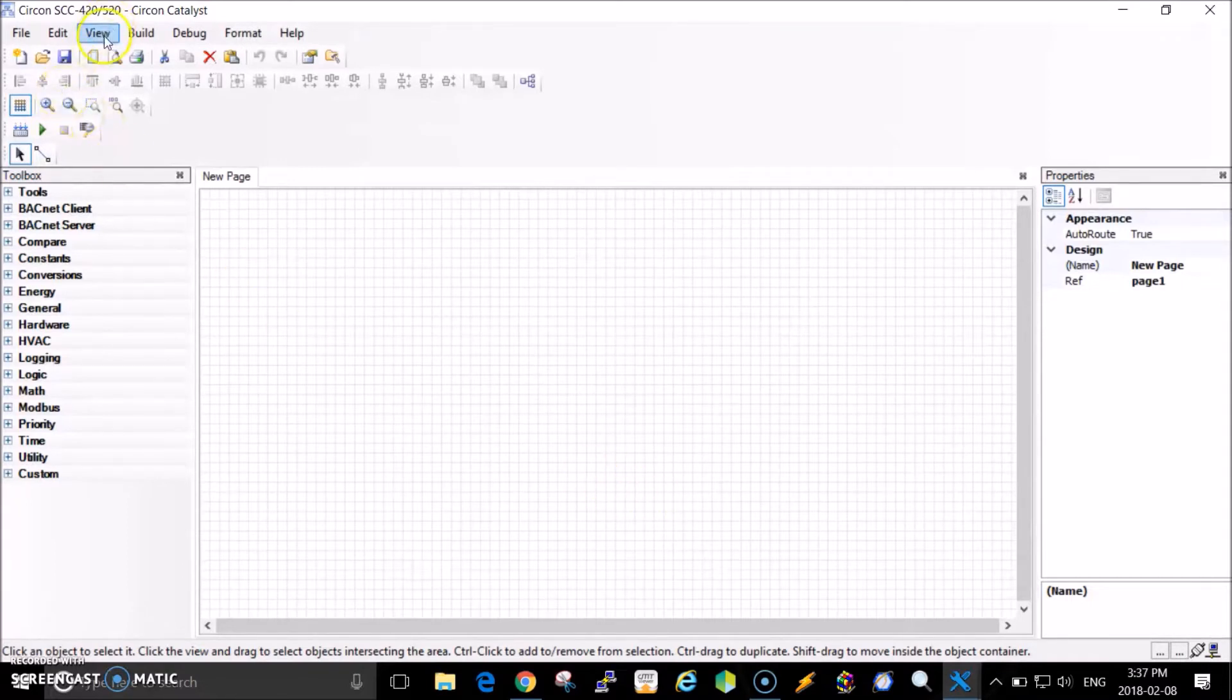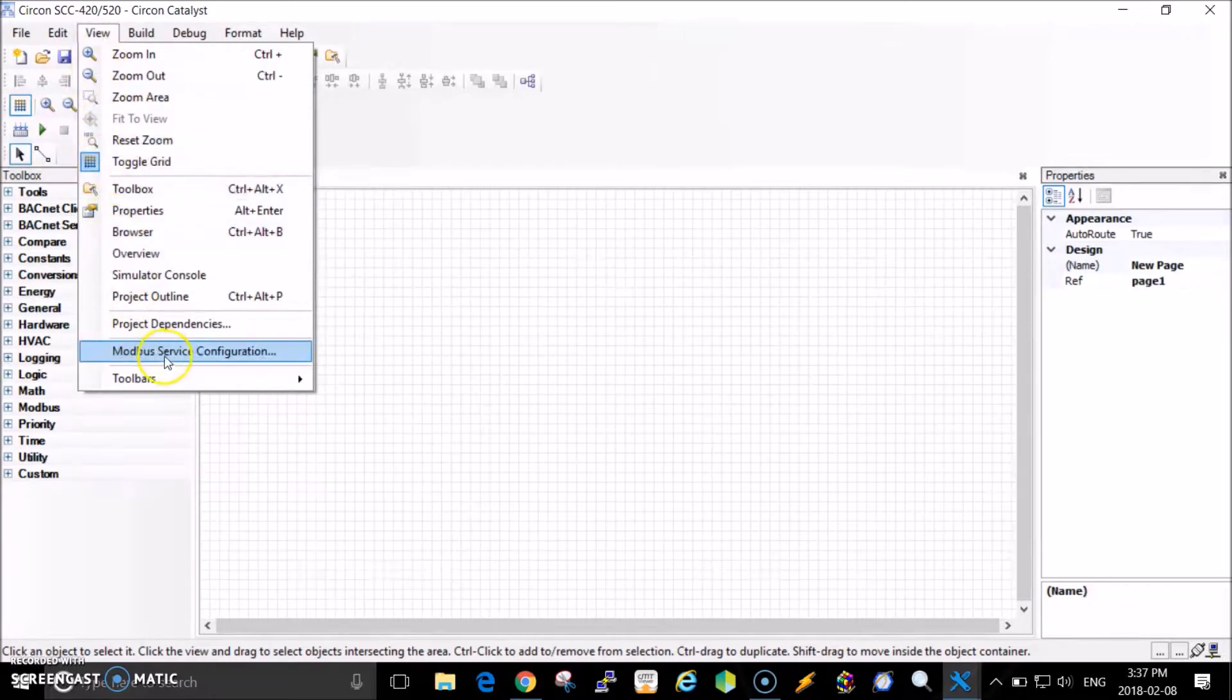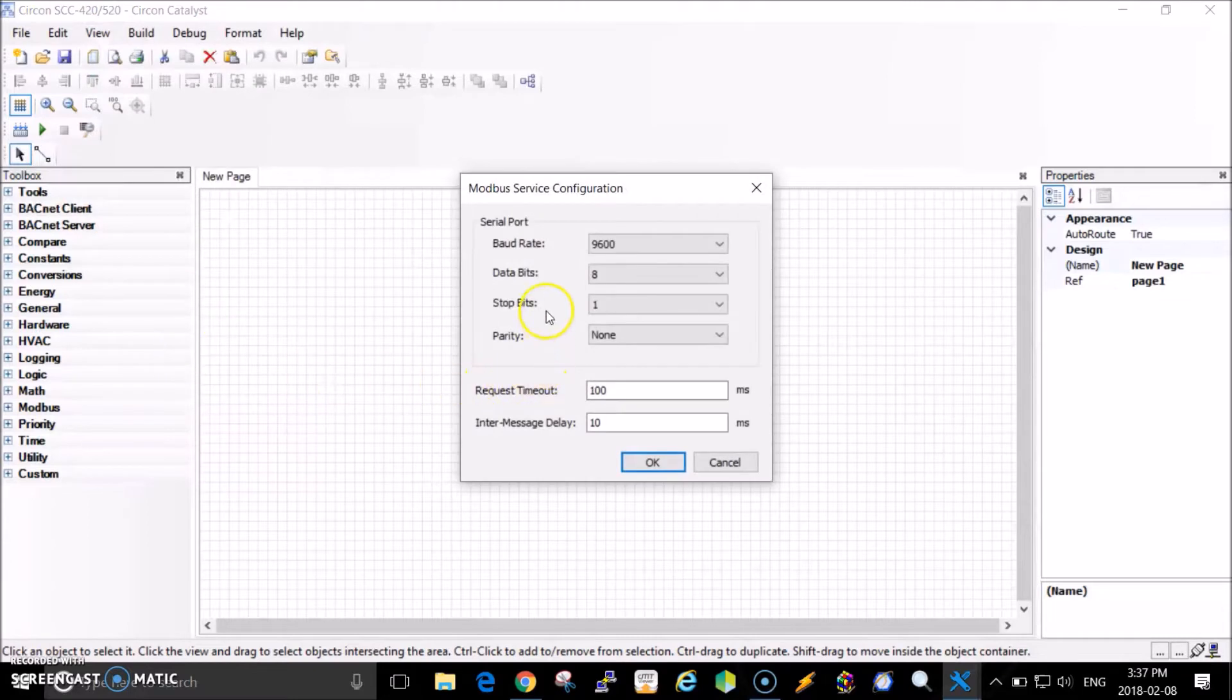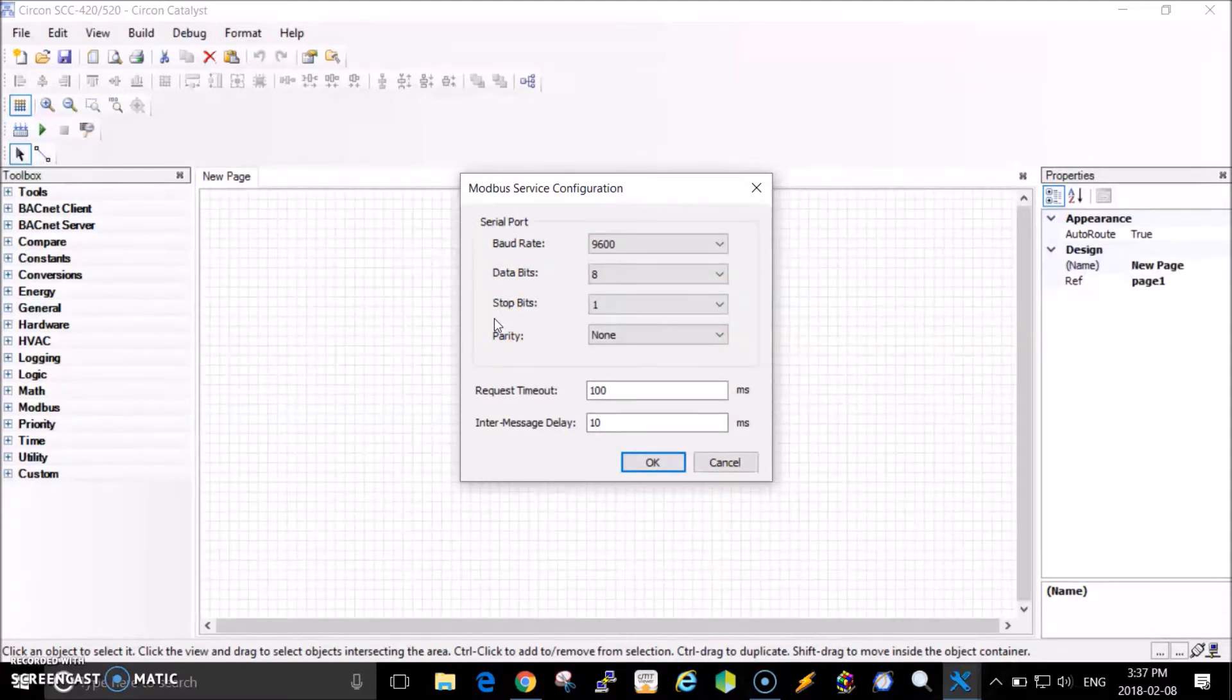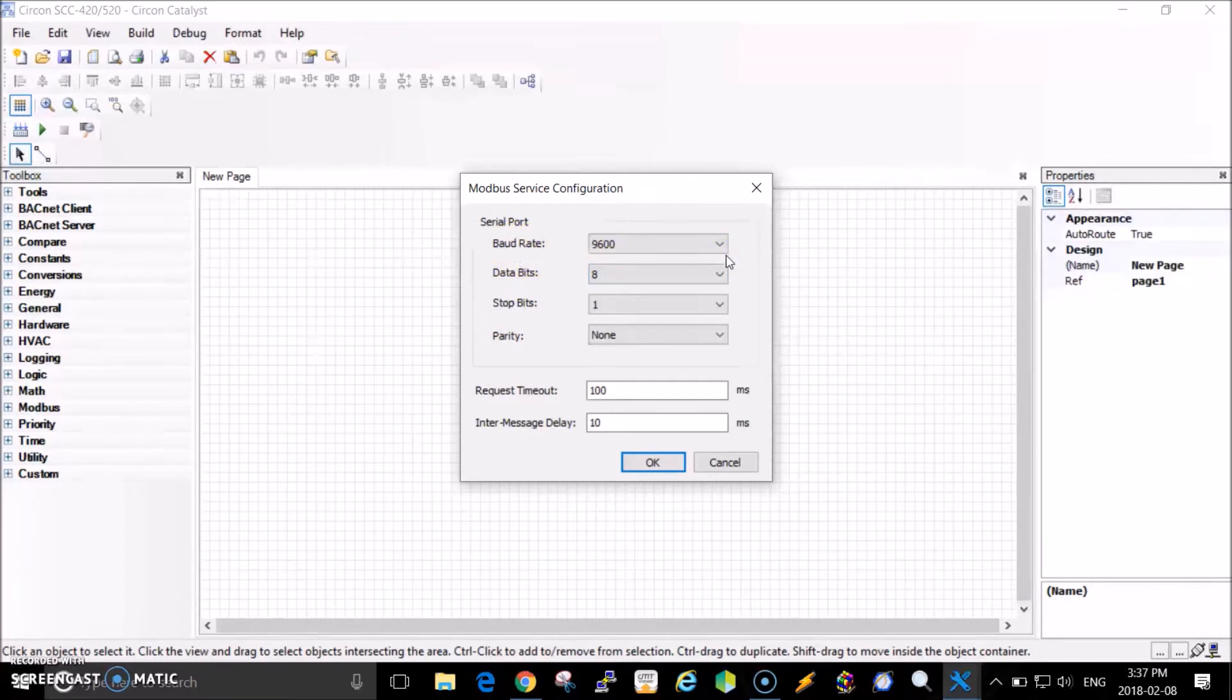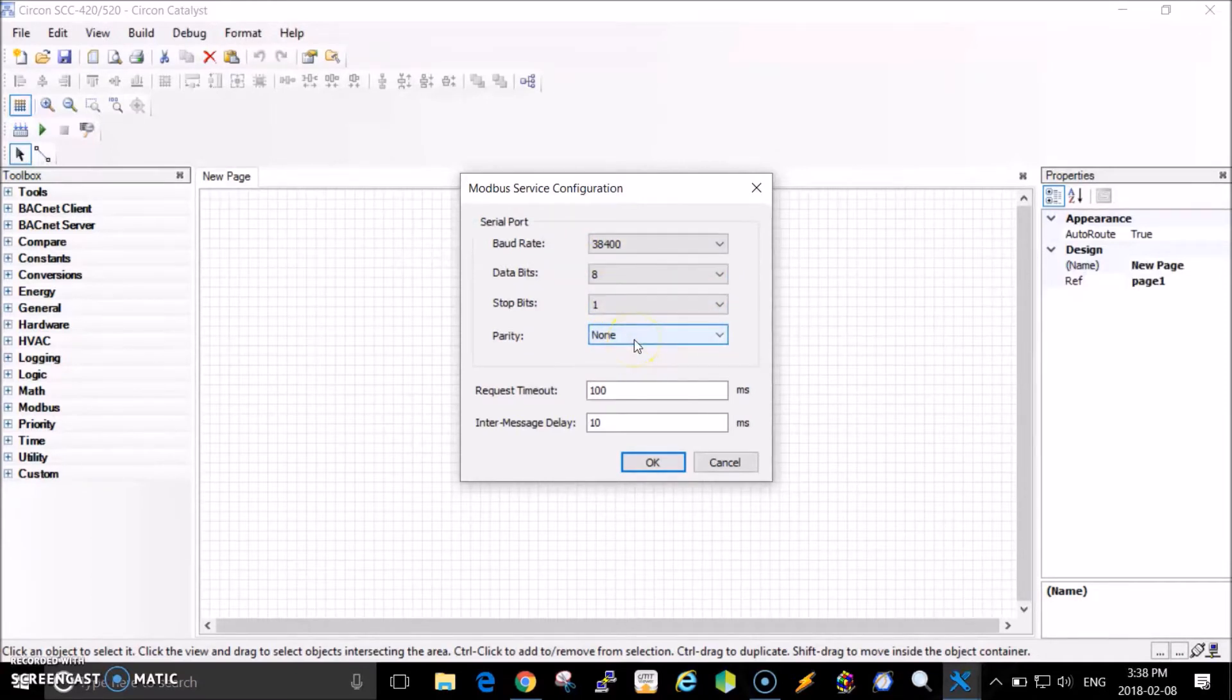The first thing I'm going to do is go under View and set up the configuration or properties of my RS485 port. That's under Modbus Service Configuration. I'll click on that and you can adjust the parameters of the serial port. This is only related to serial port number two. I know the Turbocor compressor can talk at 38400 baud, so I'll set that. I'll leave the other items as they are.